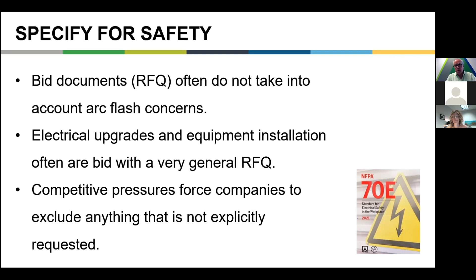Okay, so what happens if the bid documents are not detailed and we do not request deliverables related to arc flash? No pre-engineering to determine arc flash performance. That's a problem because it's far easier to remediate arc flash before the equipment is purchased. Sometimes it doesn't cost any more. Sometimes just buying a different piece of equipment will make the equipment safer.